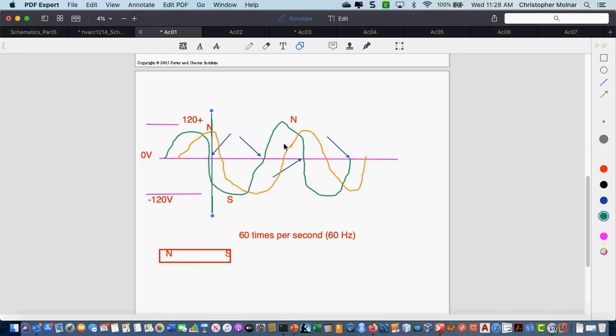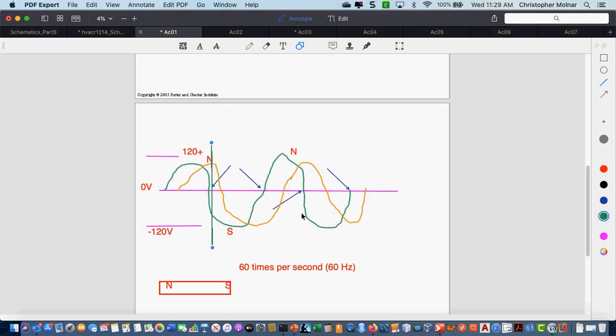It all has to do with how our sine wave works. So, seeing this, would a DC motor have a capacitor? No. Direct current motors do not have capacitors, and you're starting to see those more and more in HVAC equipment. So if you walk up to a furnace and the blower motor does not have a capacitor, it's a direct current motor. It's going to operate slightly differently from the AC motors. So as we're talking capacitors, we're strictly talking AC motors.